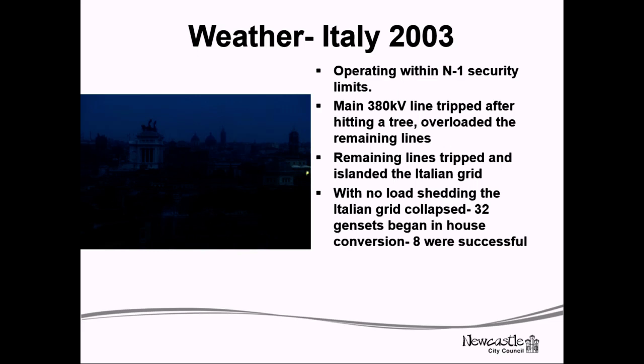One of these lines, due to weather, hit a tree and tripped. Its safety devices tripped the line off grid. Now, that in itself overloaded the remaining lines because power will flow through the path of least resistance, especially in an interconnected network. It fell onto the neighbouring Sils-Soazza line, which was now operating under 110% of its operational limits and was then outside of its thermal stability limit.